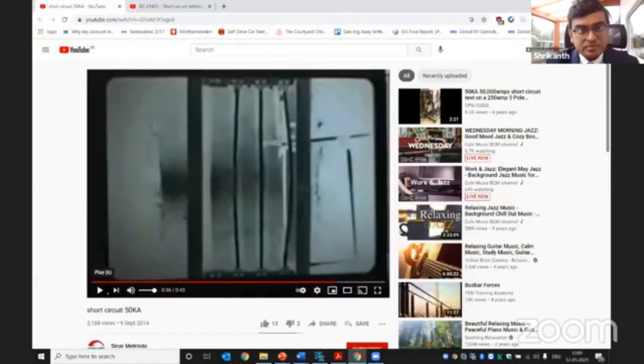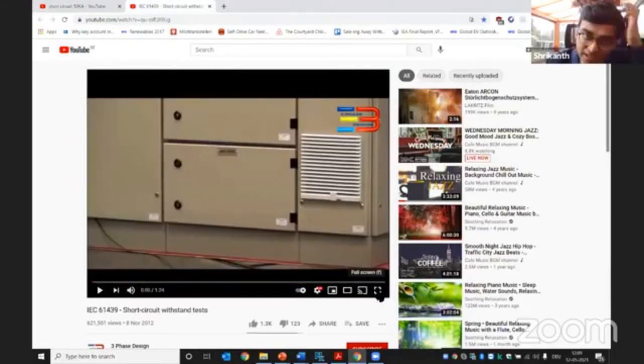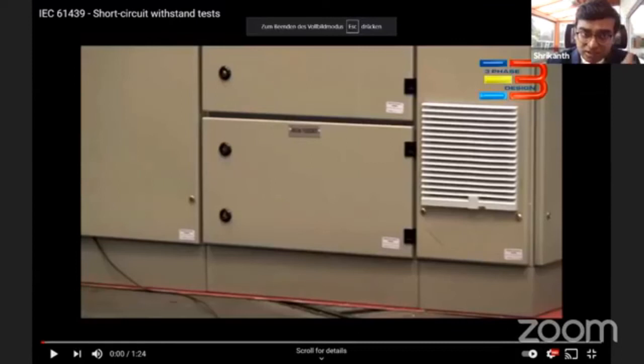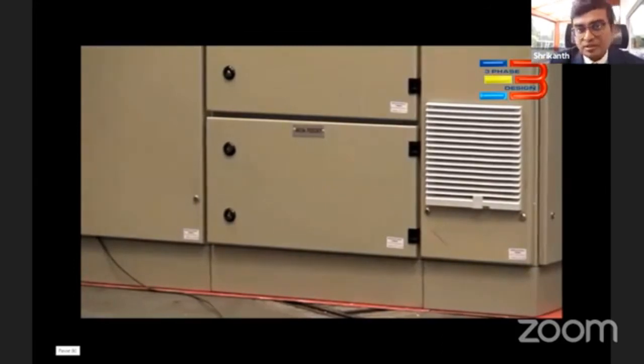So yeah, I have some test videos also right now. These are tests, I would say, which have failed the IEC 61439 tests. Here are some of the videos, just to observe what happens during a short circuit test.